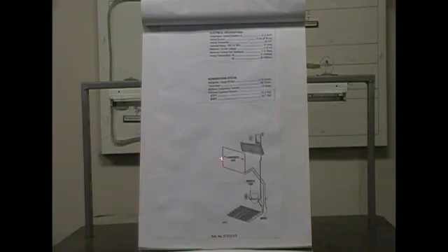And as you see right here, this is a condenser loop. At the older style right here, you have a heater, it's called a mullion heater. It costs a lot of electric. So for the efficiency and energy saving, this is their newer style. They install this condenser loop around the frame of your freezer door. So it consumes the moisture whenever the compressor is running. All right, let's look at the next diagram.